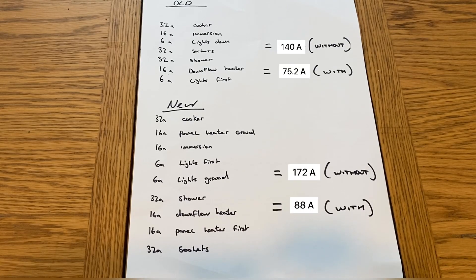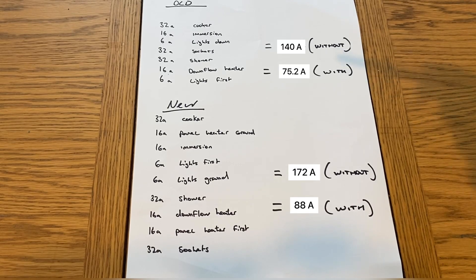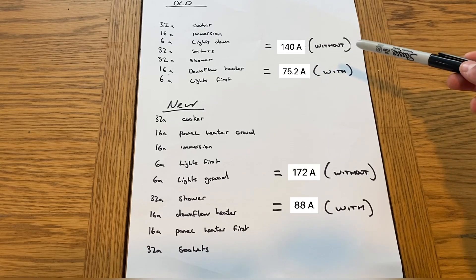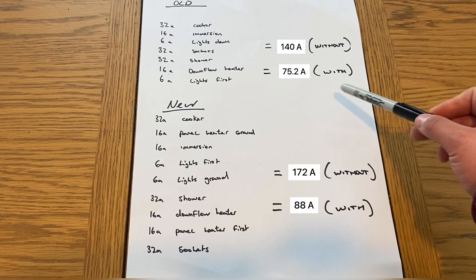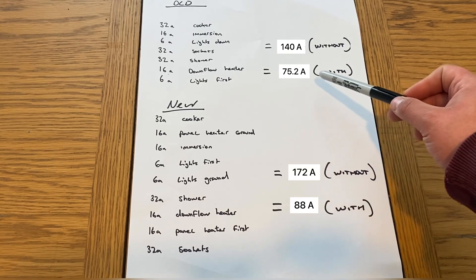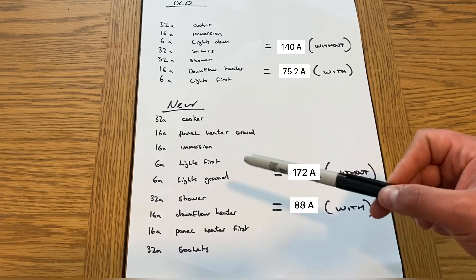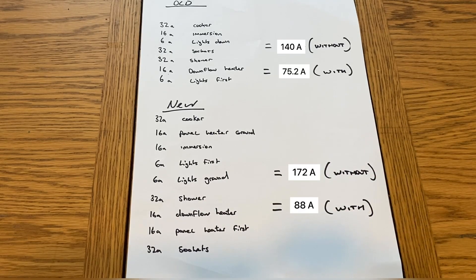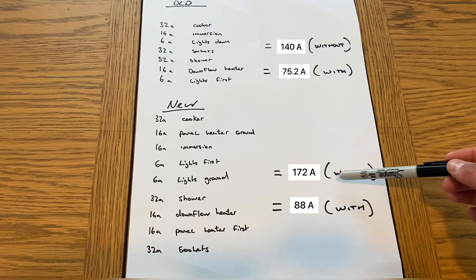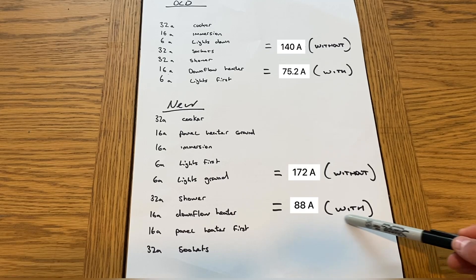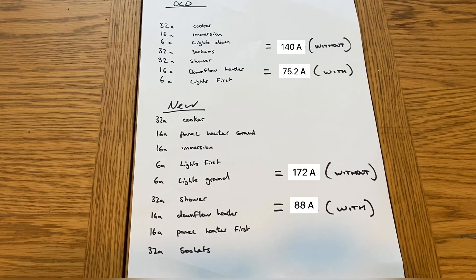It's definitely a significant difference. 140 amps without applying diversity to our maximum demand, and when we apply a form of diversity we get 75.2. And for the new one, this is the one we're worried about the most just to make sure that we can do what we're proposing to do. Without diversity 172 amps, however when we apply it it's actually only 88 amps. That means we can continue with our proposed plans. It's not going to have too much of a major effect on the installation.